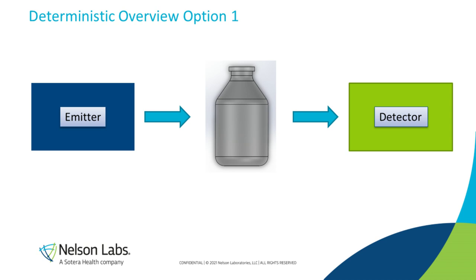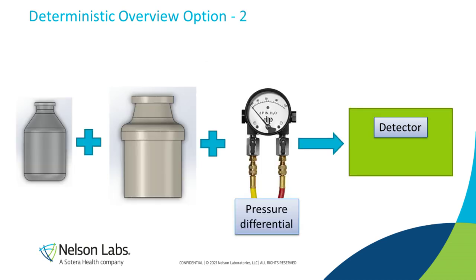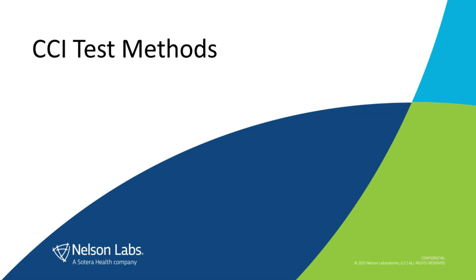The deterministic methods break down into two categories. Option one applies to high voltage leak detection and laser headspace: an emitter sends a signal through the test sample, and a detector picks up the signal and interprets it as either a leak or not, based on a pre-established numerical pass-fail threshold. The second option applies to mass extraction, pressure and vacuum decay, and vacuum mode tracer gas: the sample is placed into a fitted chamber, a pressure differential is created, and the air is passed through a detector — measuring mass flow, volumetric flow, or helium — then interpreted against a pre-established pass-fail threshold.